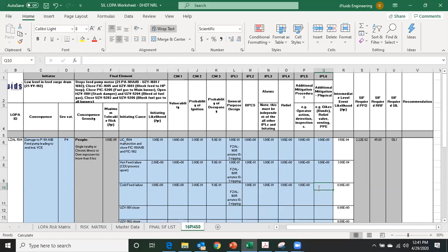Likewise, USZV close also. USZV close will normally be very rare because all these valves will be SIL 2, but they will not be checked. So I will take once in a year because I am giving SIL 1 only, as there is no proof test. Once in a year means 0.1. Vulnerability 1, probability of ignition 0.3, probability of occupancy 0.3. These are all conditional modifiers. And there is one more trip that is helping me to trip the event, even when the low level comes.